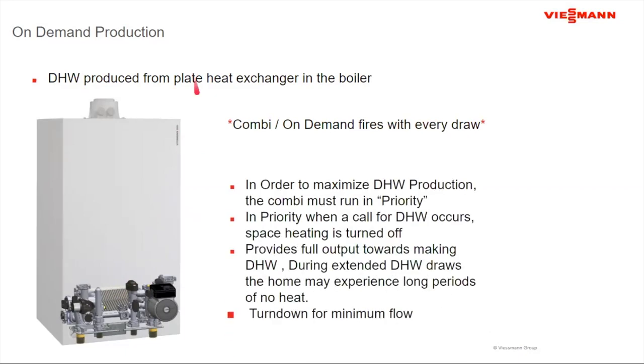Okay. Now, the other thing that happens when I do a combi boiler is that everything has to be in a priority mode. Priority means that when the call for domestic hot water happens, space heating shuts down and the full output of the boiler goes into generating domestic hot water. When I do an indirect, I also have this option available, but with an indirect, I can take it out as well. And we'll talk about that when we get there. So in priority, space heating gets shut off.